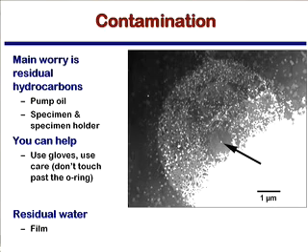There's another machine that has been brought into use more than 10 years ago now called a plasma cleaner. And what you do is you take your sample holder and you clean it in an argon-oxygen plasma to get rid of the extra carbon on the sample and sample holder, and that can help a lot. We have one of those with the advanced microscope. So that's a real issue.